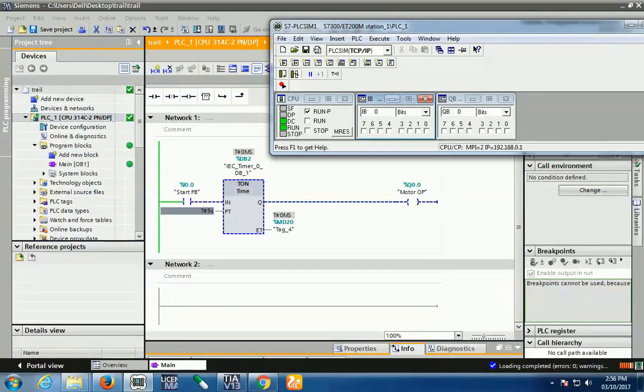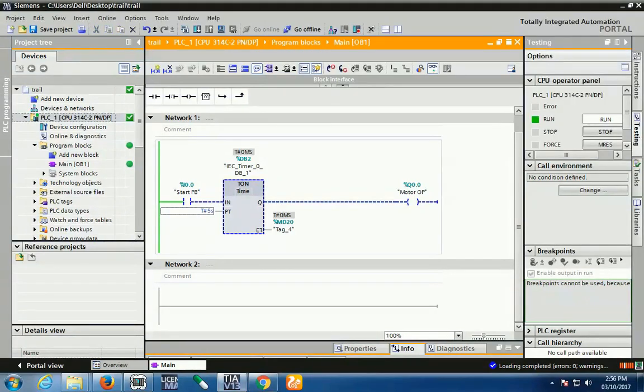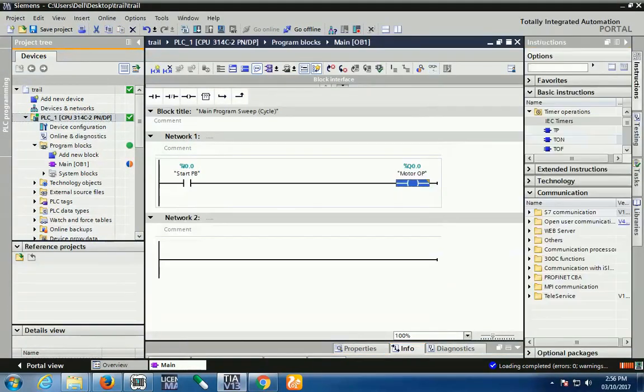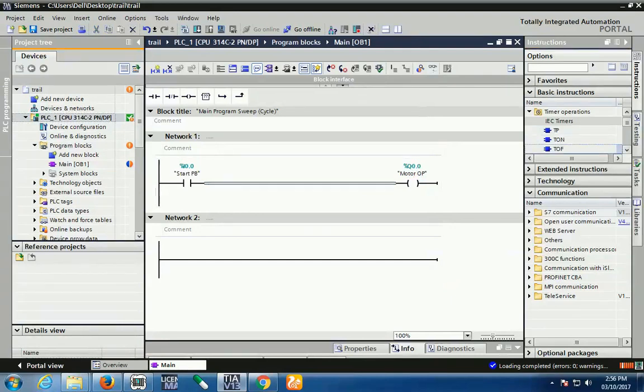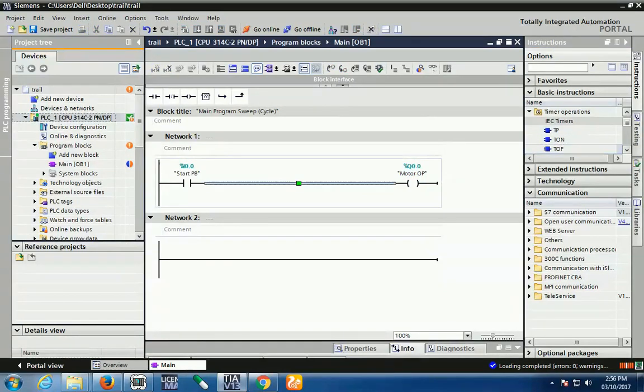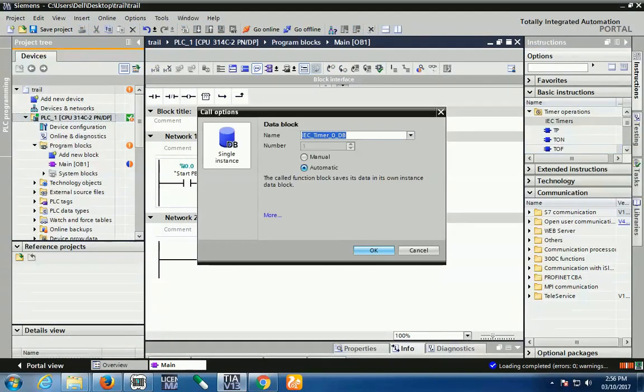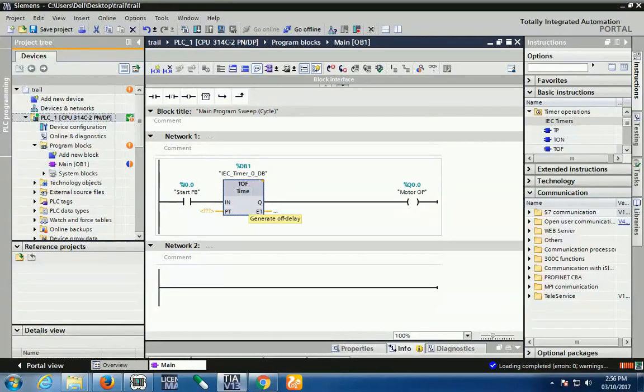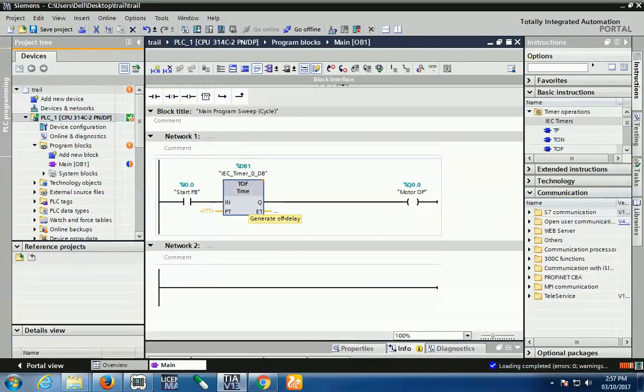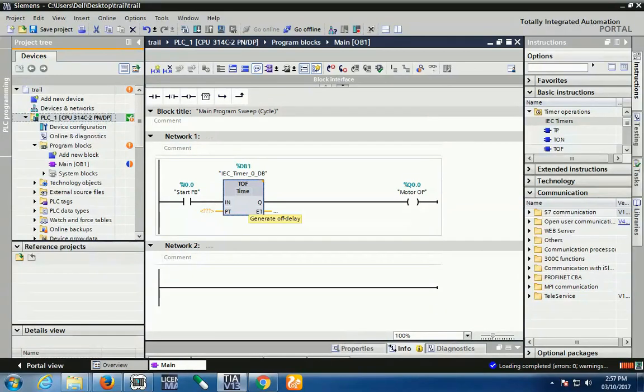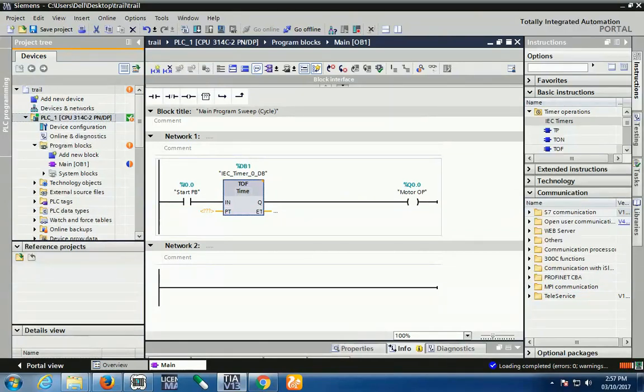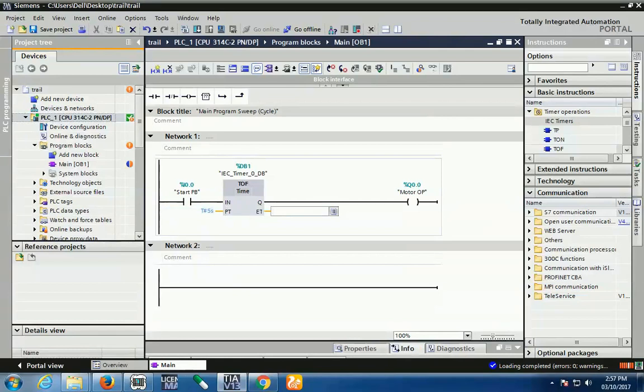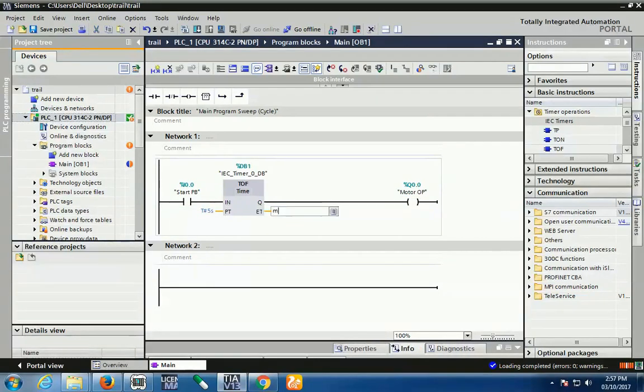After the time is complete, your output should turn on, and when I release the enable command, my output should turn off. This is the timer configuration of TON. The last one is TOF, meaning off-delay timer. Off-delay timer function means if I stop the cycle - suppose I have one motor, if I press the start button my motor should turn on, and when I press the stop button, my motor should turn off after 5 seconds delay. In this case, I set 5 seconds, and this is my motor. If you want current time shown in HMI and SCADA, just set it here.